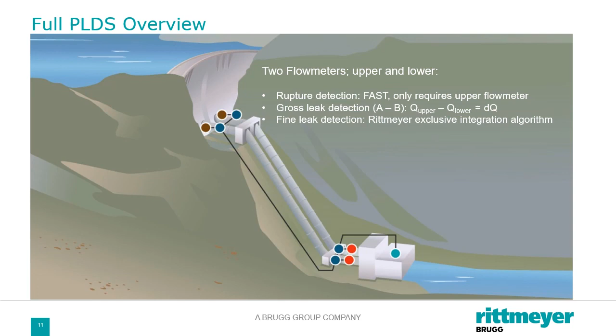Looking at this in a little more detail, the rupture detection can act quite fast. Ours is a full flow meter, so it isn't going to get fooled by unequal flow distributions like a pitot tube could. It's going to respond very fast, and there are cases where you'll want it to actually do an autonomous gate closure. It can be a single-ended device, much like it would be with an overspeed. And we have some advanced functions we can put in to fine-tune a rupture plus detection, if you will, specific to your site.